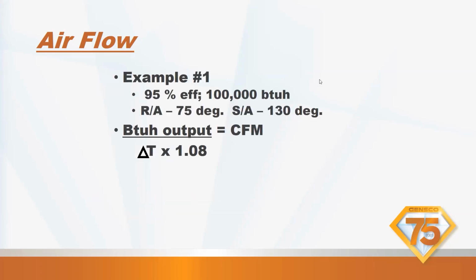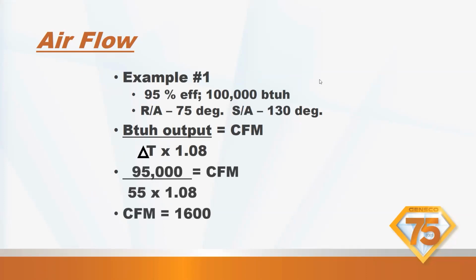So here's the example: 95% efficient, 100,000 BTU furnace. Return air is 75 degrees. Supply air is 130 degrees. We're going to do our calculation: 95,000 divided by 55 times 1.08, and that's going to give us 1,600 CFMs. So those of you who live in a higher altitude, you should probably do this calculation right here with your number and see what your CFMs really are. They're probably going to be higher. And if they're more than 10%, you're going to want to reduce your airflow to get it down to the 1,600 so that you're not having issues with your compressor. Okay.